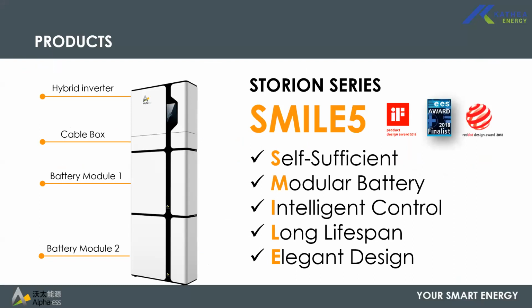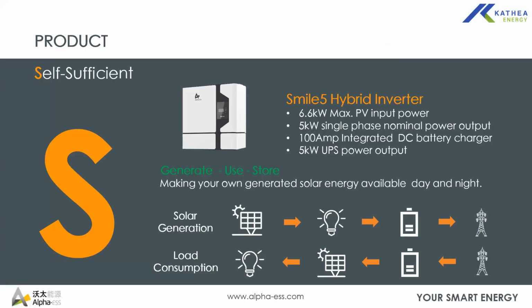Okay. So we'll basically look into all these functions in detail. So the first one being self-sufficient. So the system has a built-in MPPT, which can take up to 6.6 kilowatt PV input, which can actually help to oversize your system in terms of your PV array. So the system has two built-in MPPTs, which take in 2 strings with a minimum DC voltage of 125 volts to 550 VOC. So we can simply wire your strings.